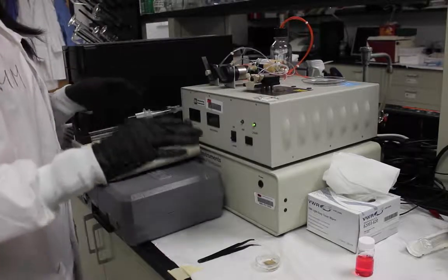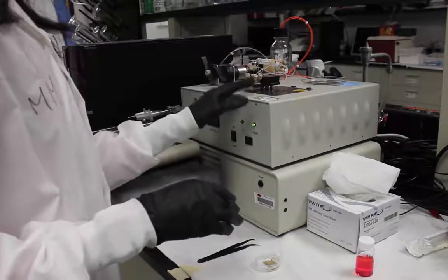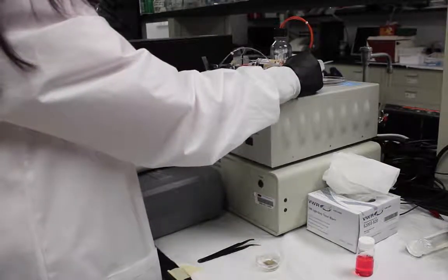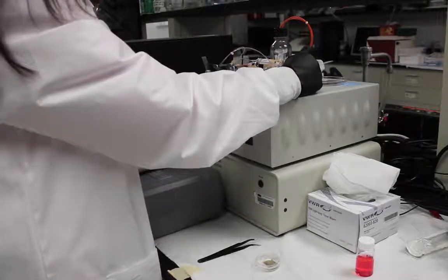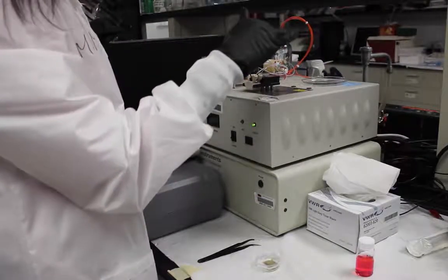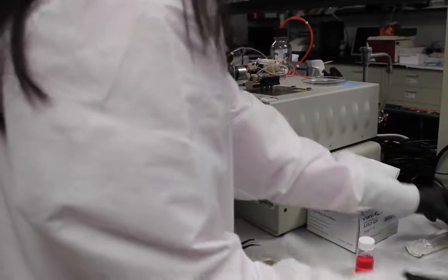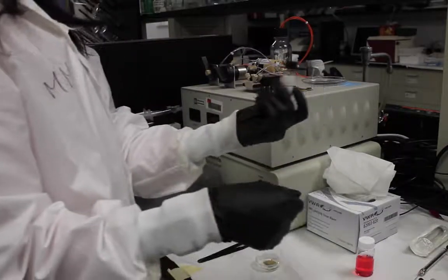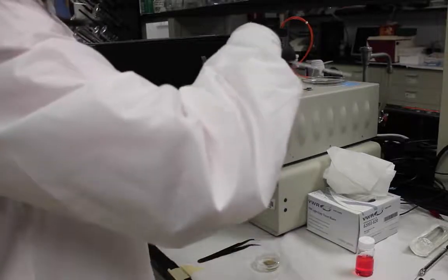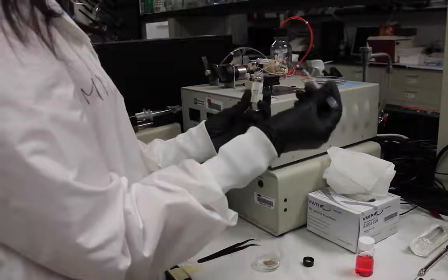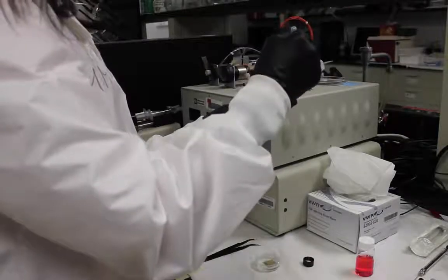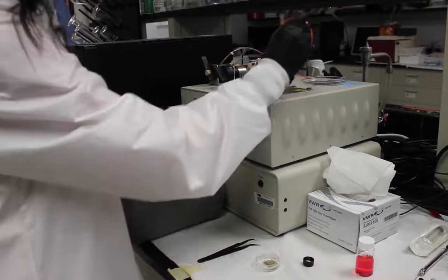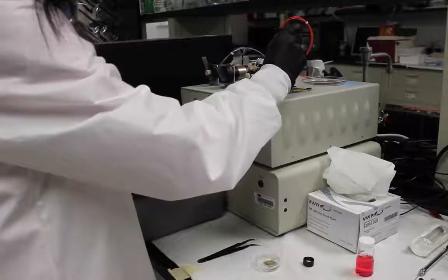So to start your SPR experiments, this is the prism on top here. If there's a viewing window also, you can see a straight black line on it. The first thing that you do is use an index fluid, which is provided by the company. It has a known refractive index unit, and it is important to use that in calculations. So you take a little bit of a drop of it, about 2 millimeters in diameter, and put it in the center of this prism.